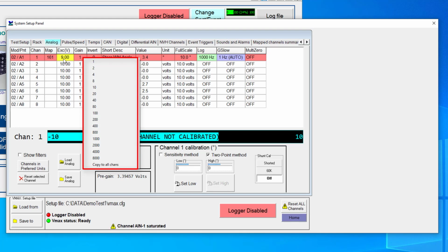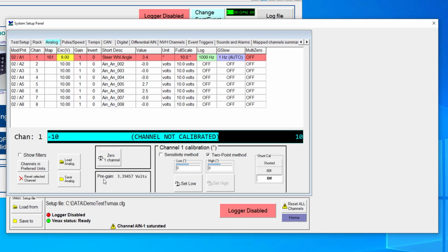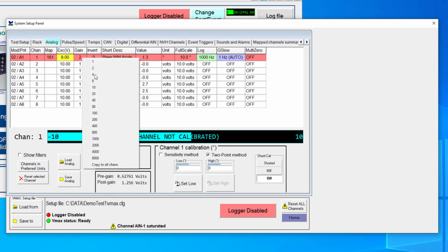So right now with a gain of 1, essentially anything that I bring in, I am not doing any amplification to that signal. So you can see I go down to 0.4 volts all the way up to 9 volts by completely going through the stroke of this particular sensor. Now if I was to change this gain, anything that comes in, I'm essentially going to double its output. And in many cases with a millivolt type of sensor, you might be using gain settings in the 400, 800, sometimes even 1,000. You can go all the way up to 8,000 for very, very small millivolt type output signals.